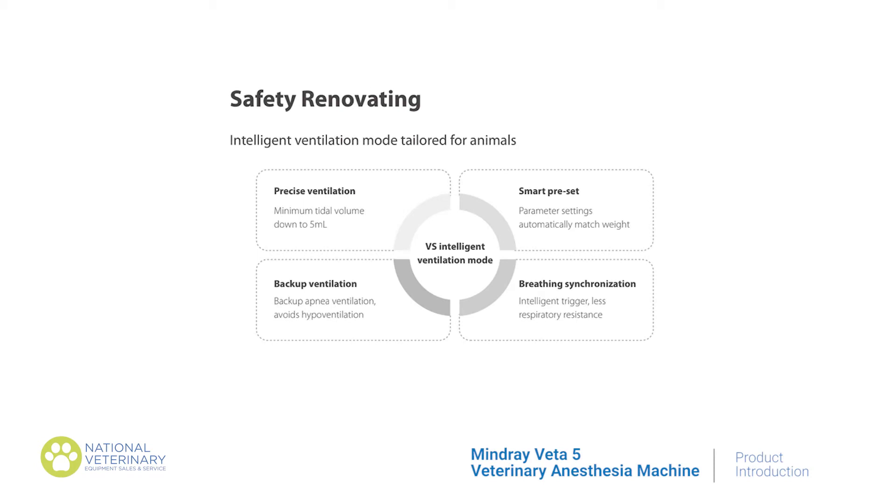The Mindray Veta 5 focuses on redefined safety, offering a dedicated veterinary anesthesia solution for both patients and veterinarians. The Veta 5 offers low tidal volume for small animals, a minimal tidal volume of 5 mls, and it can also support a minimum patient weight of just one pound. The APL or pop-off valve operates based on a number scale, providing precise pressure control to avoid barotrauma.